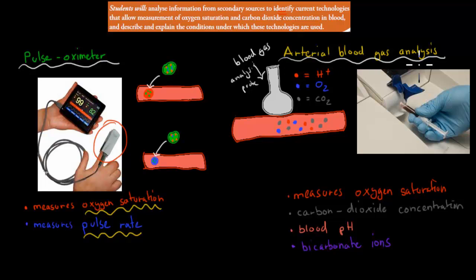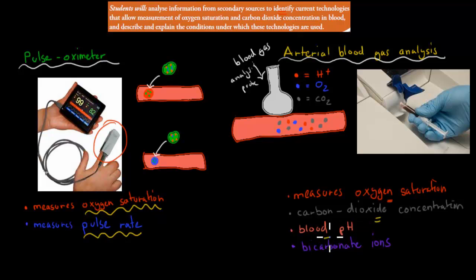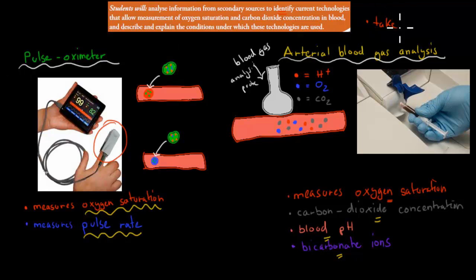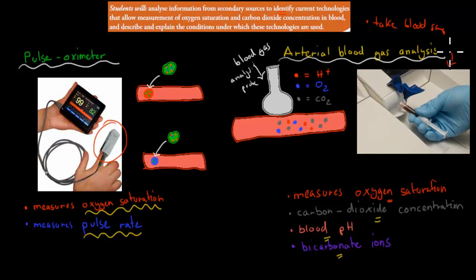The other technology is arterial blood gas analysis. It measures oxygen saturation, the same as the pulse oximeter, but on top of that it also measures carbon dioxide concentrations, blood pH, and bicarbonate ions. How this works is you actually have to take a patient's blood — you take a blood sample — and then you put it into one of these machines. This is a blood gas analysis machine.